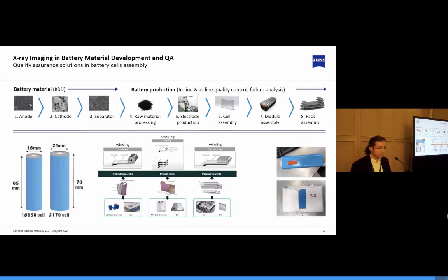Of course, at some point you will hit the limitations. The limitations for the way the X-ray operates are basically the penetration lengths of the X-rays. What you capture in the detector is a signal, which is the attenuation of the X-rays when they pass through the sample. So that signal depends on two main factors: the density of the material and the thickness of the sample. So if you go to battery packs, you will need more X-ray energy to penetrate those battery packs, and your resolution will be somewhat limited. You cannot think of getting nano resolutions on those types of samples, because there is a trade-off between those two, power source and the resolution.